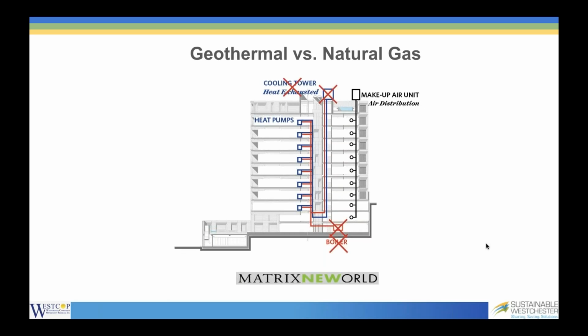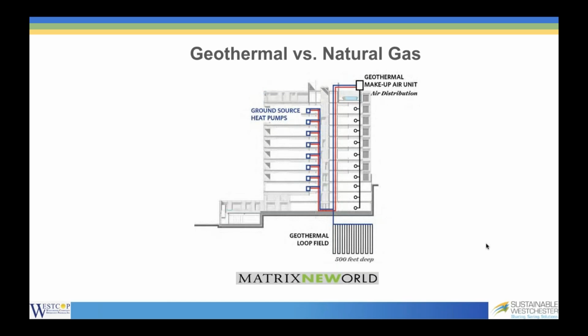With a geothermal system, you no longer need a cooling tower or a boiler. You still use the same traditional components of pipes and heat pumps, but with geothermal, you have a geothermal loop field, which is underneath the building or next to the building.